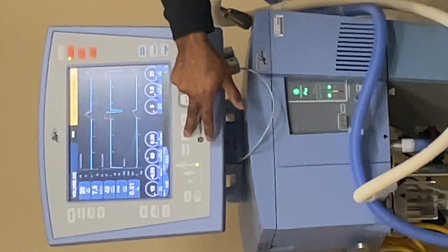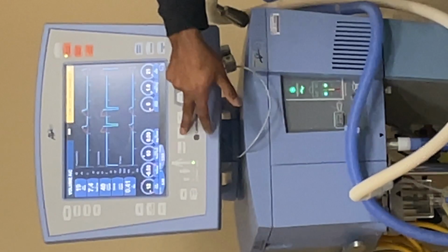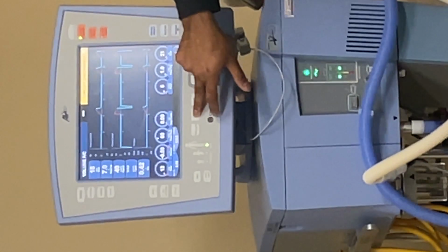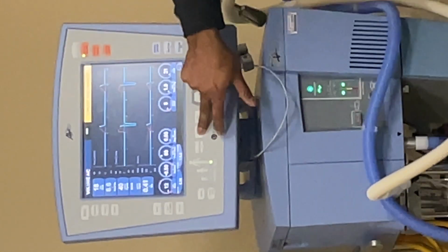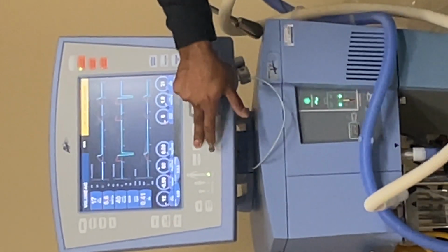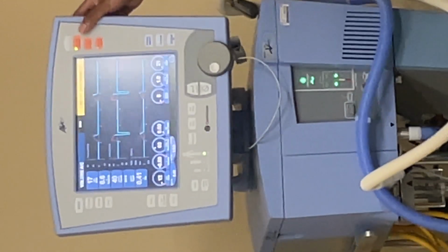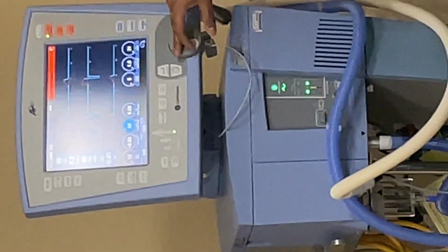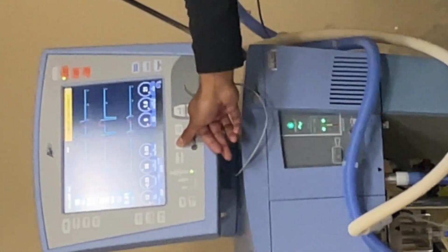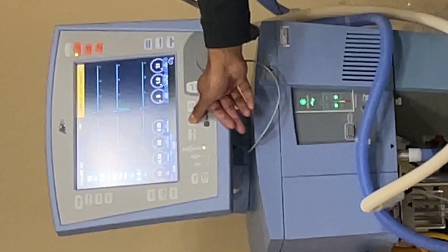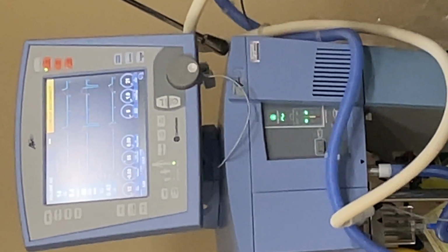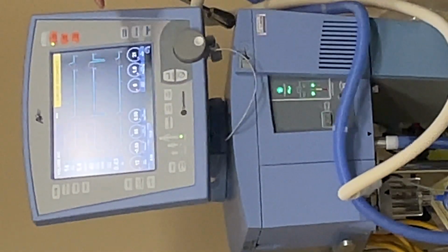I'm going to hold after the, wait a second. It has to be done at the end of the inhalation. Why is it not doing it? Hold on a second. This is something that respiratory would do for us. We wouldn't do it. This is because the test lung has so much resistance that it's canceling out. It won't read now because the compliance on this is too high, so it's canceling my inspiratory hold. It's trying to force it in.